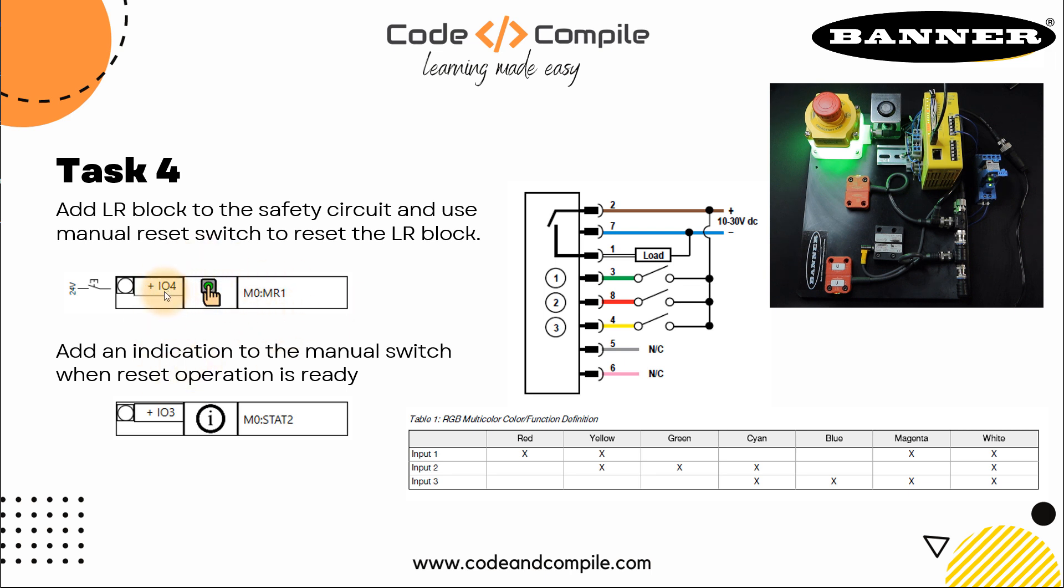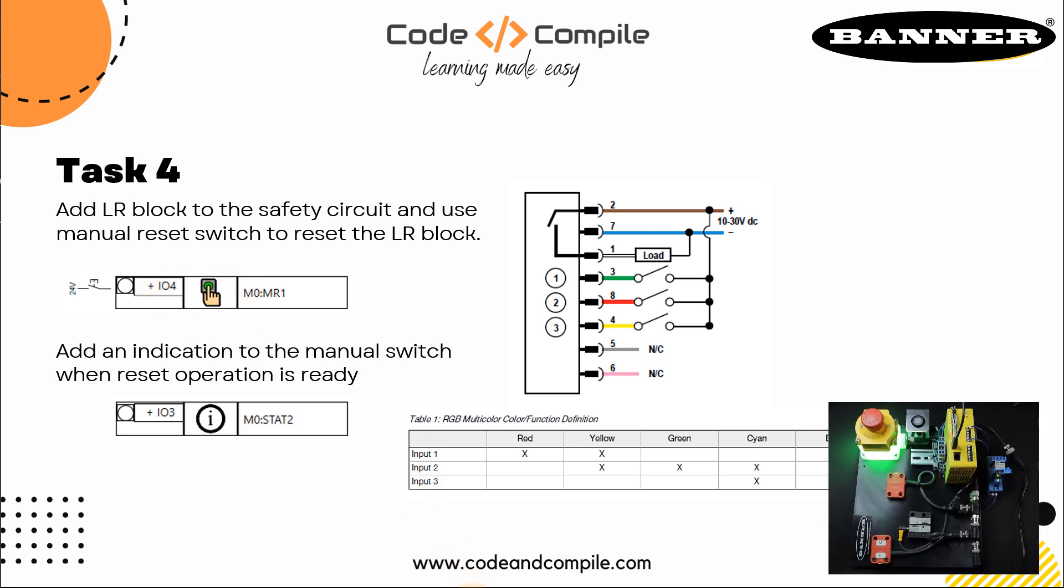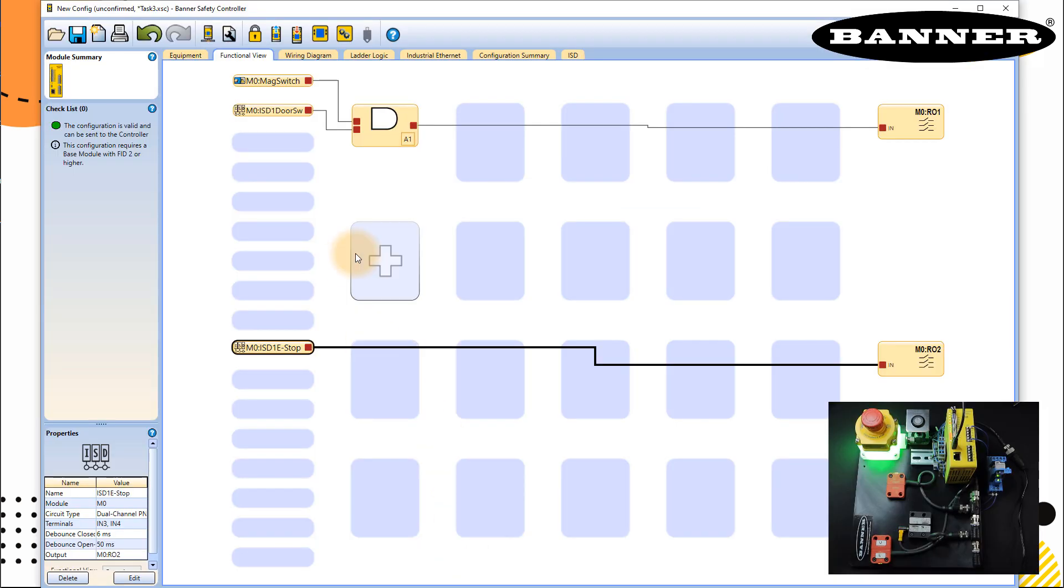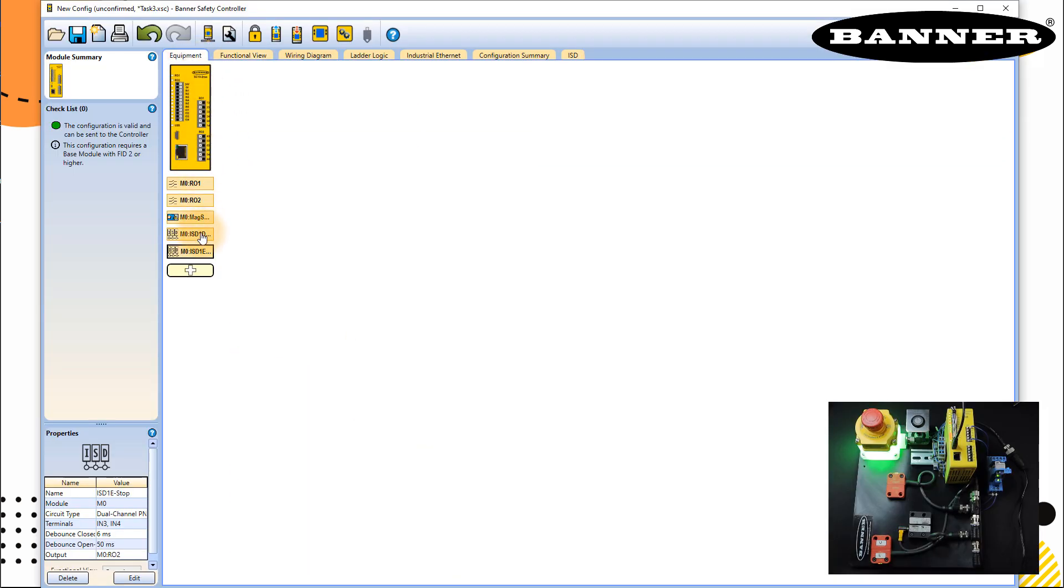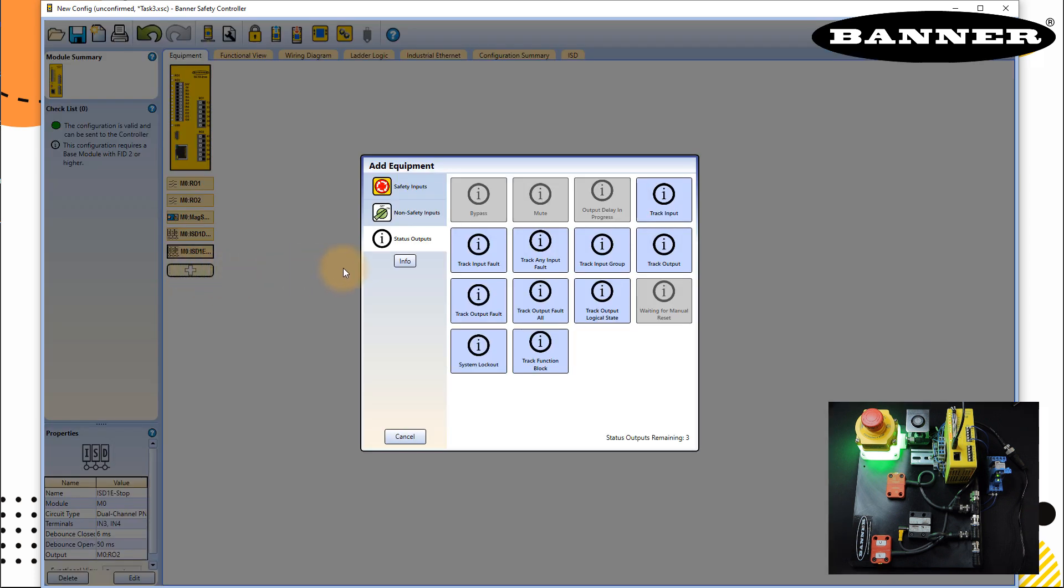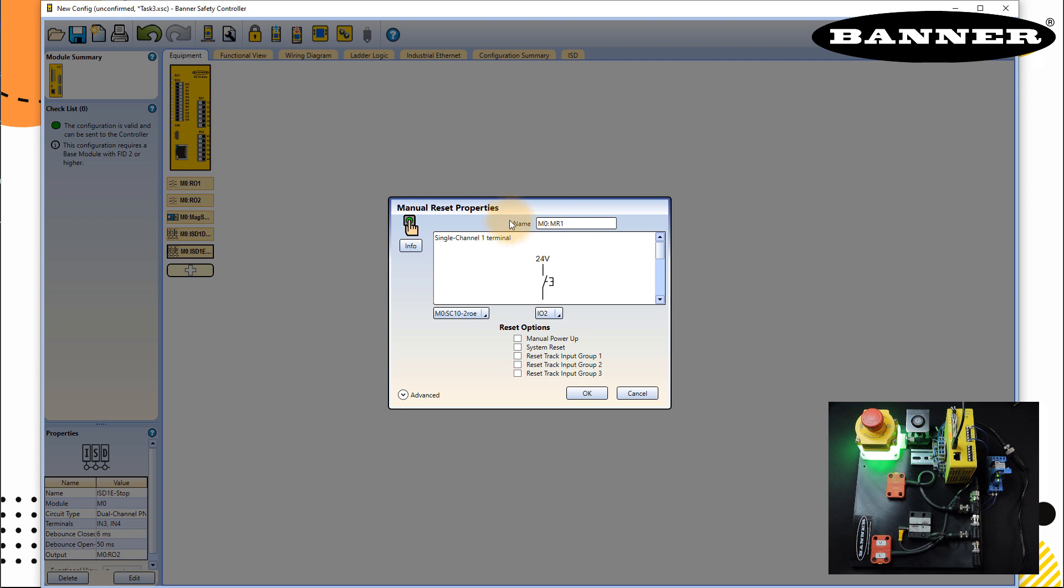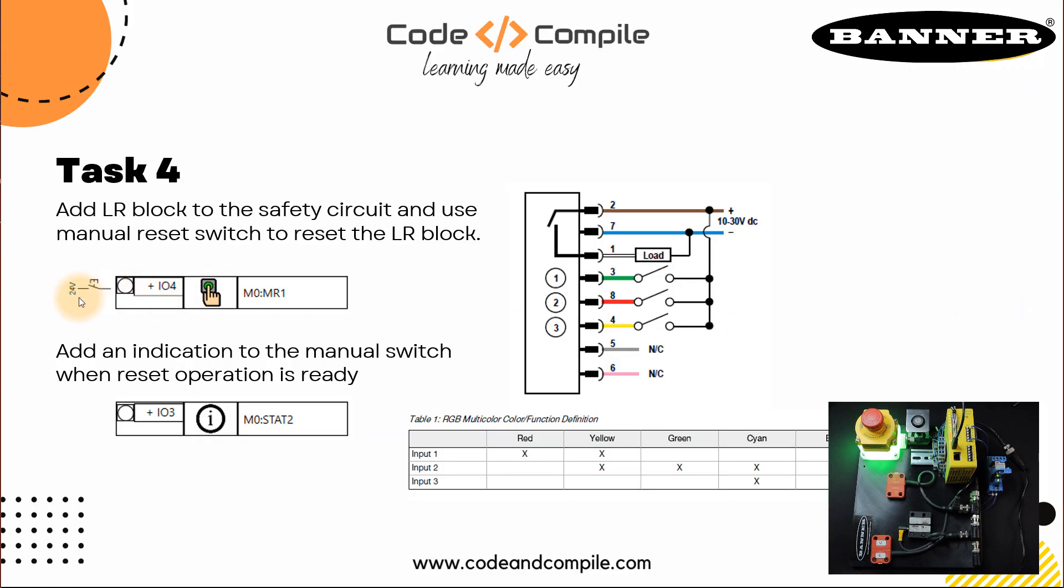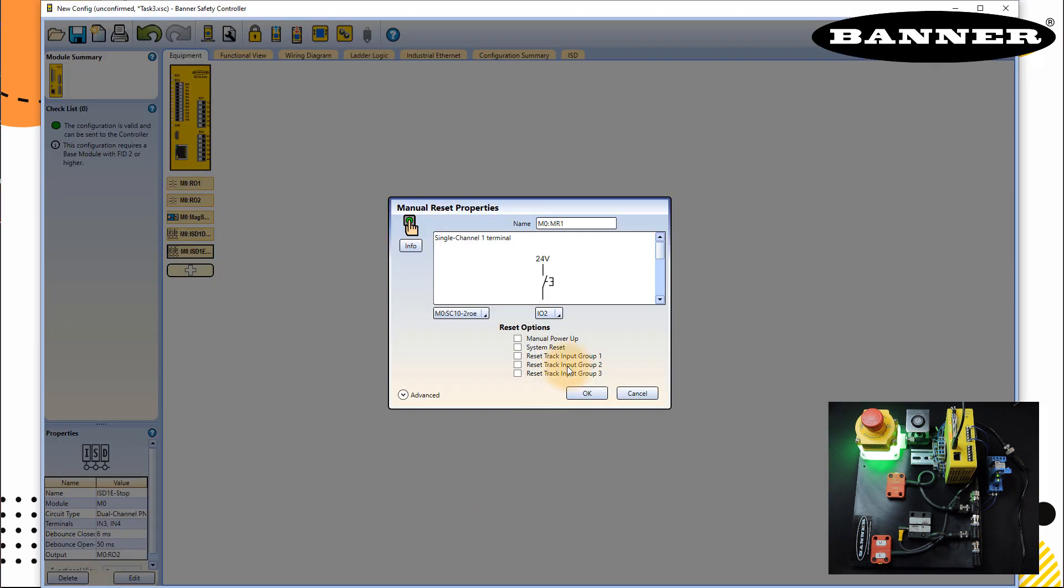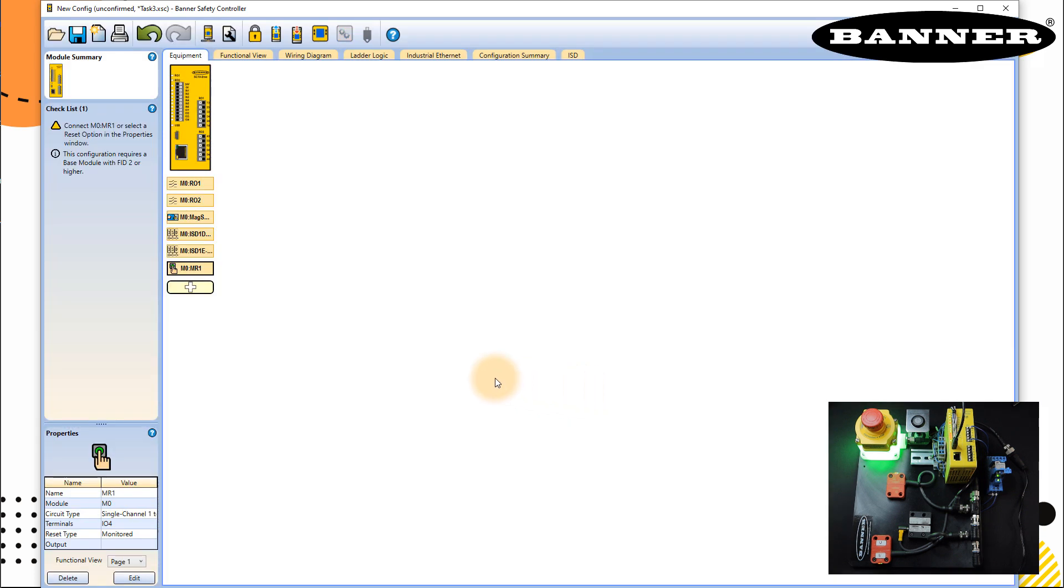Let's see, first we take the controller input IO4 with the switch. I will go back to my equipment and go to plus. Remember we talked about it in the presentation, this input is a non-safety input, just for reset. It's not a safety sensor, not a safety input, so we call it non-safety input. Now we're going to select manual reset. Just remember the diagram, this is just single terminal connection to IO4. So here I will select my IO4 terminal, everything else is okay. I can rename that, I can call it MR, manual reset one, which is okay. In my case, nothing to change, click okay.